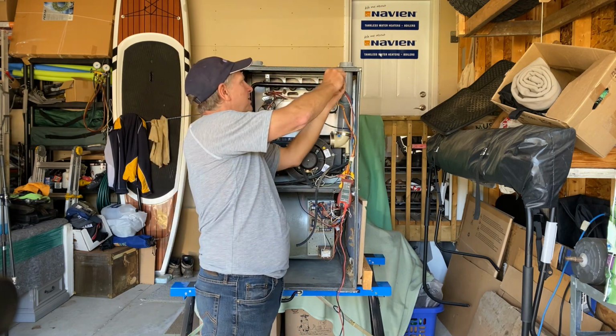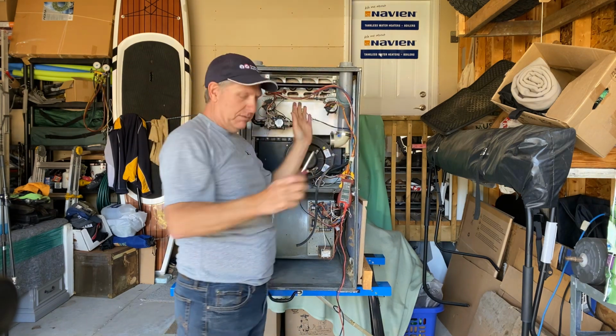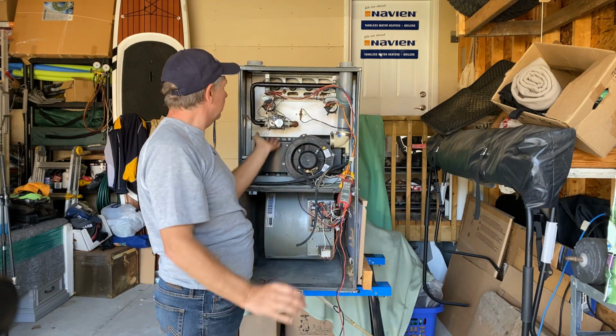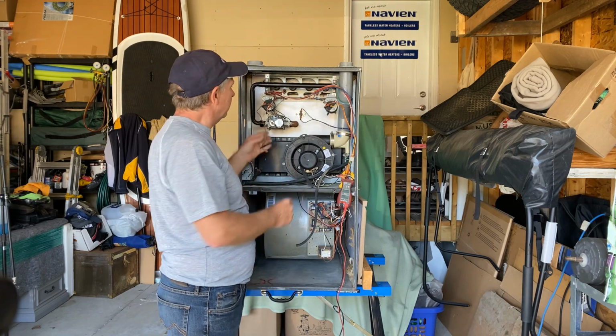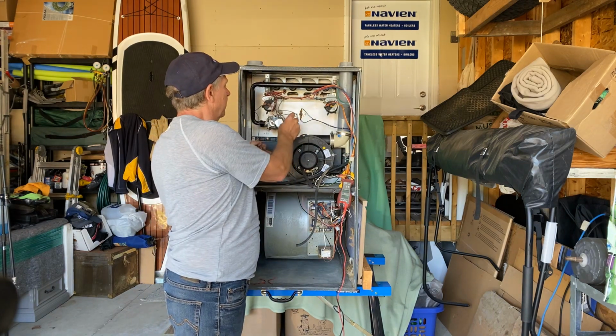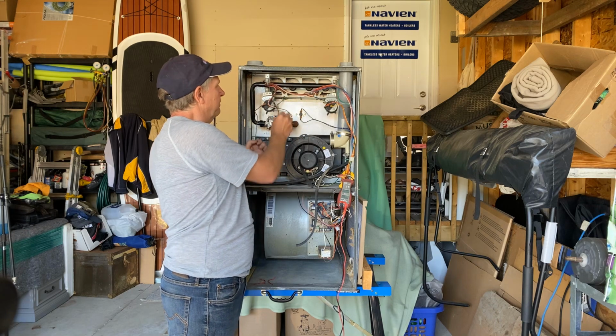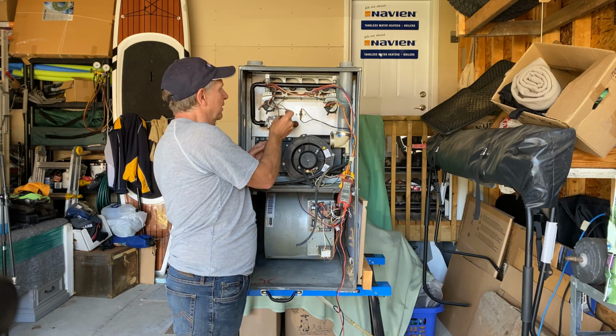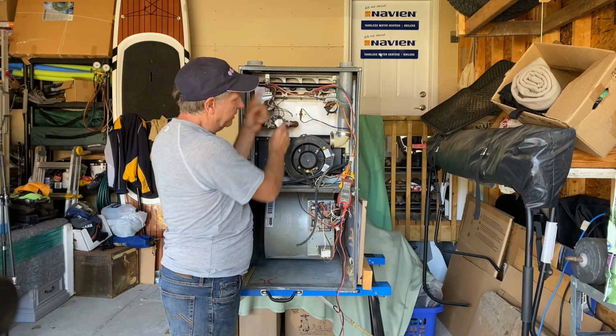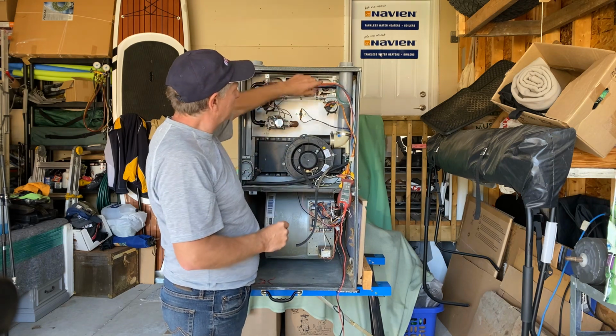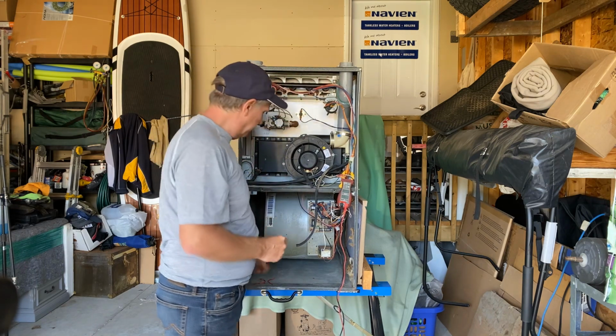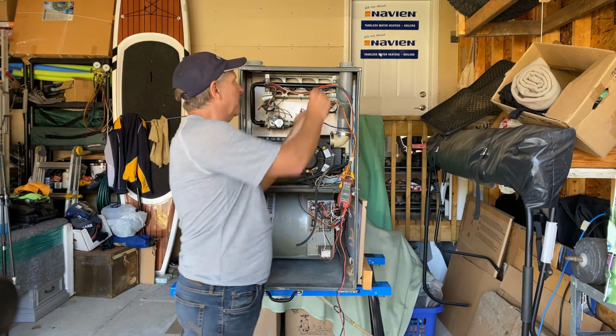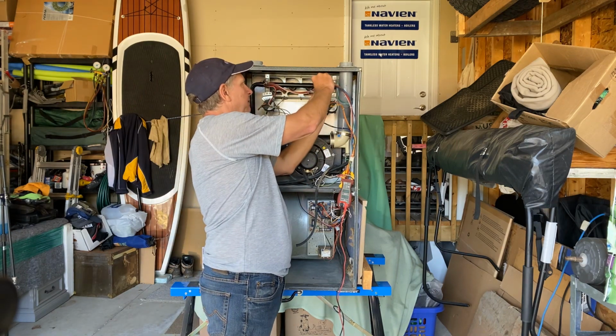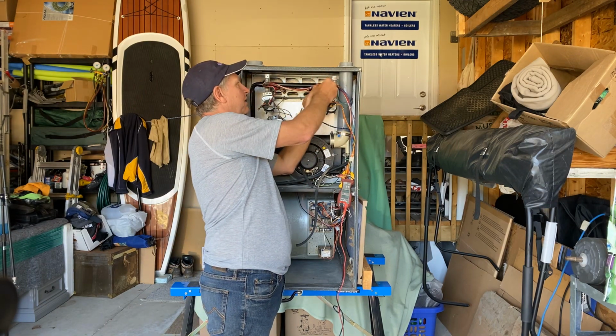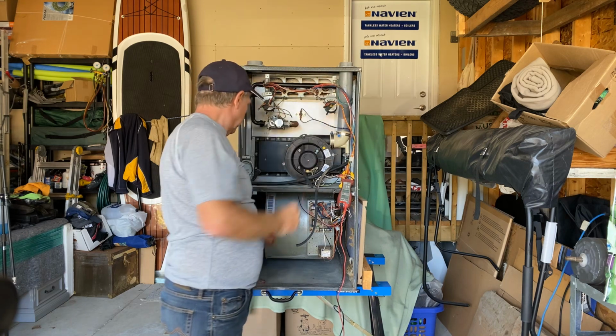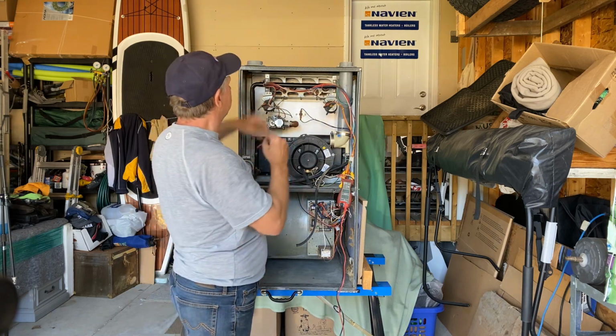So there, our burner assembly is back in place, ready to go, all put back together. Now I would reconnect my piping. Okay, I've got my 2 wires for the gas valve, put those back on. I put the wire back on the flame sensor, so that's good, and I would just fasten these wires up so that they're not flopping all around, keep things neat and tidy.